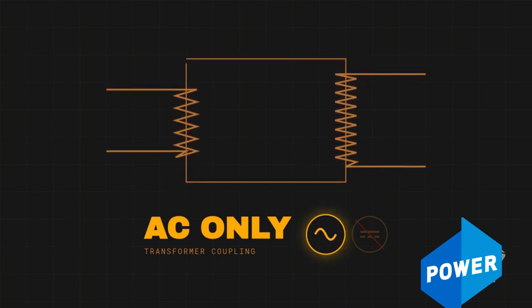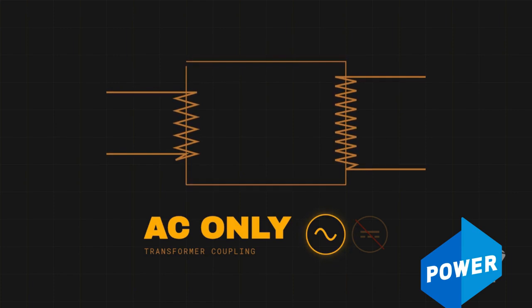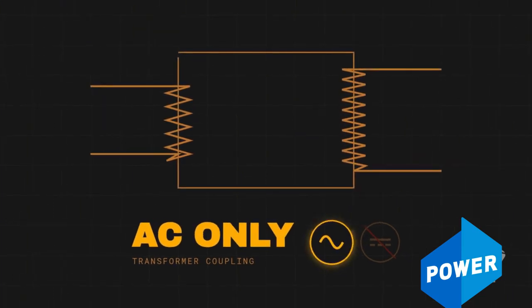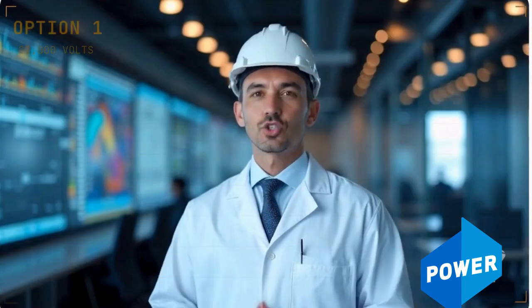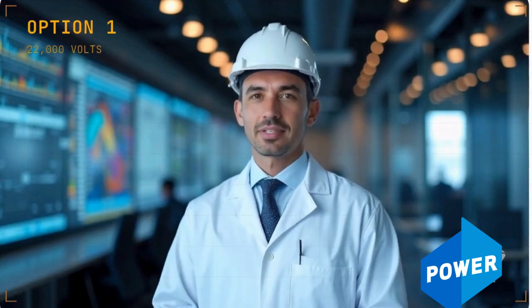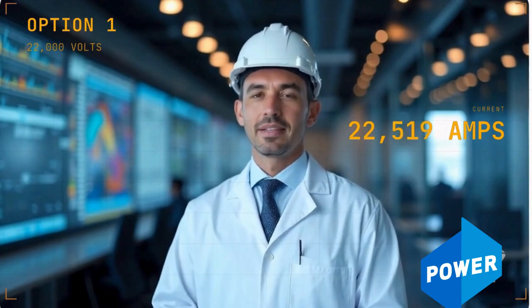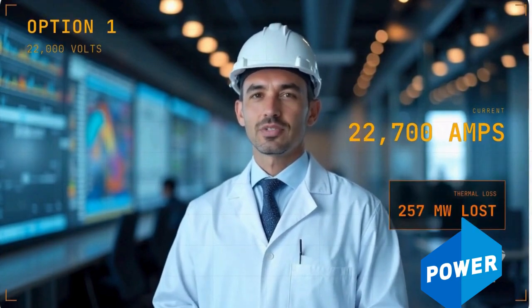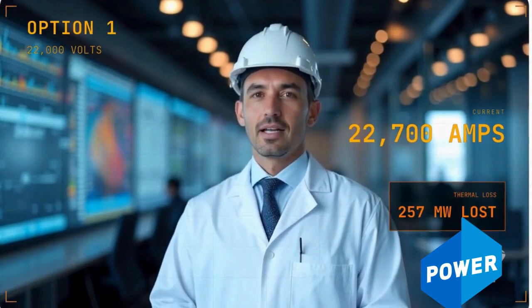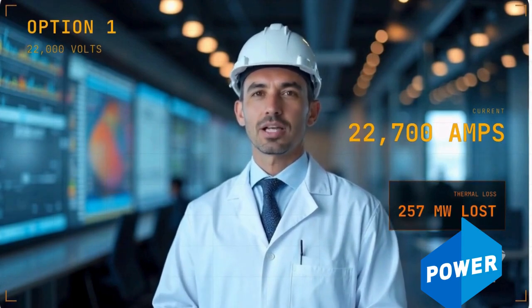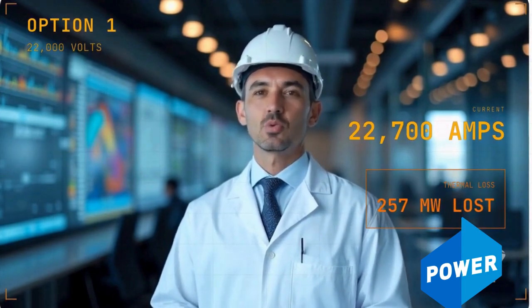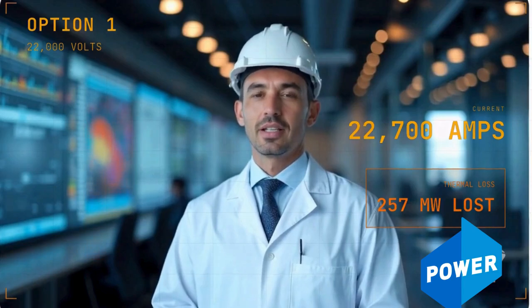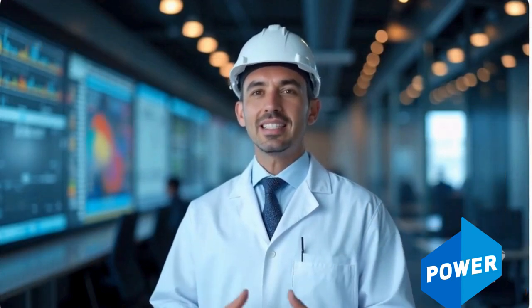Alright, let's make this crystal clear with real numbers. Say a power plant generates 500 megawatts. Option 1: transmit at 22,000 volts. Current needed is about 22,700 amps. Power lost in the line equals I squared times R, roughly 257 megawatts lost as heat. That's more than half your power gone, just heat in the air.